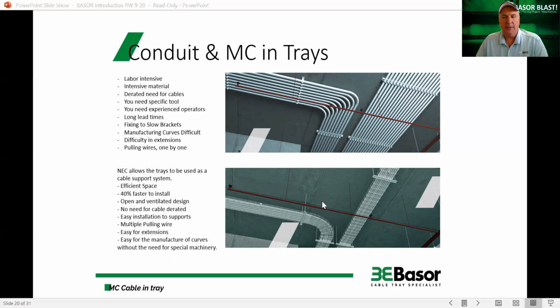You can put a cable into a tray and save a lot of labor. You don't need to derate your cables. It's much more efficient to manage moves, adds, and changes. You can span longer distances, so it costs less for supports. Pulling wires one by one, or tube by tube, is difficult, but you can pull multiple bundles of MC cable through a tray, saving time, money, space, and weight.